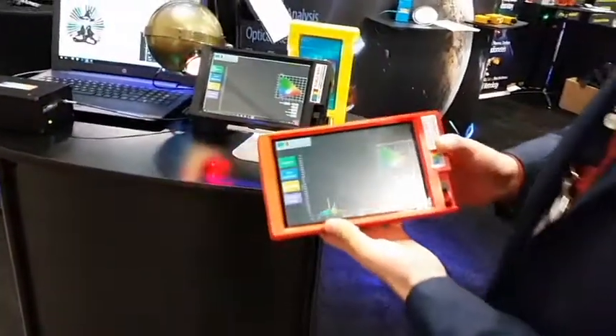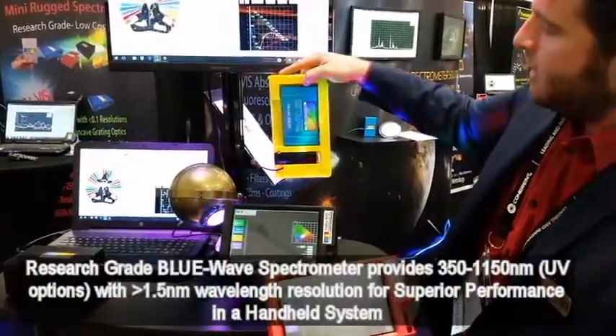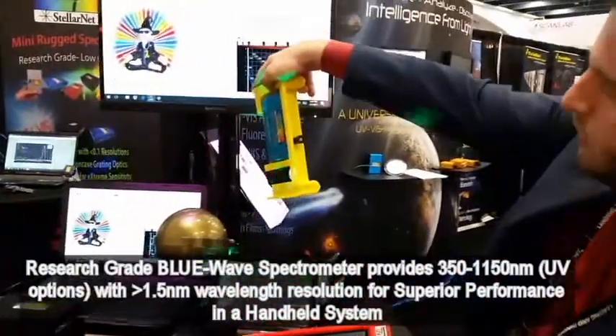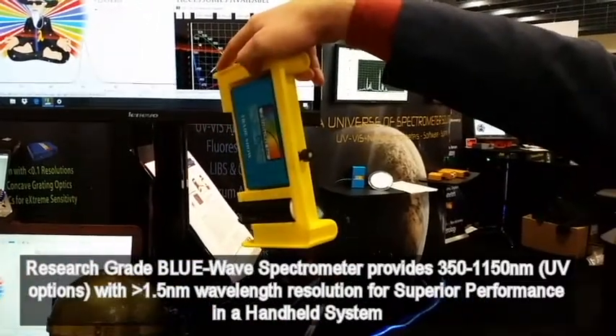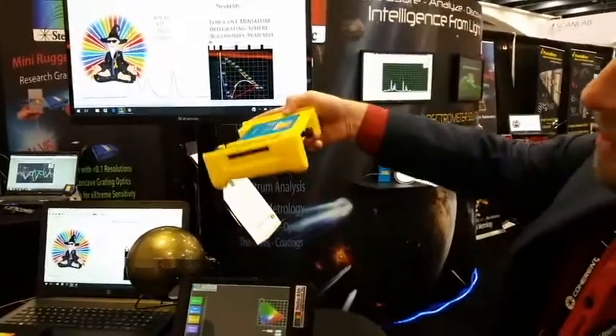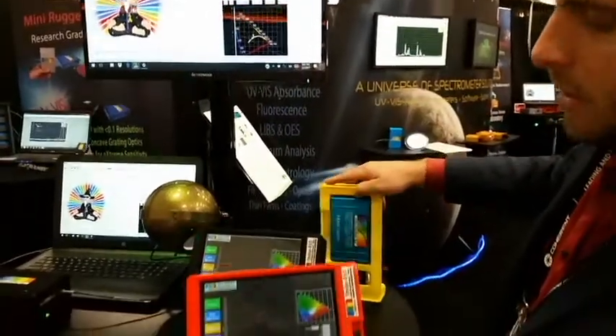You can see here that we have our research grade Blue Wave spectrometer mounted in a nice rugged case. We also have a cosine receptor that connects directly to the Blue Wave spectrometer, which will go from wavelength 350 nanometers to 1150 nanometers. The StellarNet handheld system also has a USB hub to easily connect to the tablet computer.